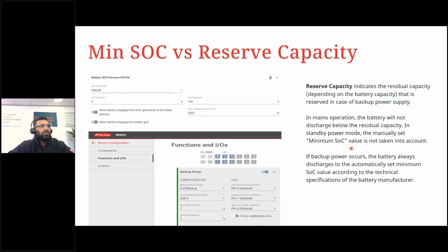All right, so where do we set this full backup? As we mentioned earlier, you can go into device configuration, functions and IO, and here you can turn on backup power mode, and set the backup power mode to full backup. But one of the topics you can see here is the reserve capacity. So what is the difference between minimum SOC and reserve capacity? Reserve capacity is the battery capacity that is reserved to be only used in backup scenario.